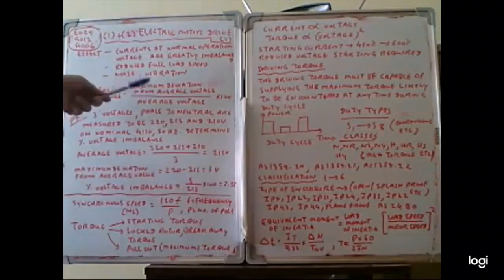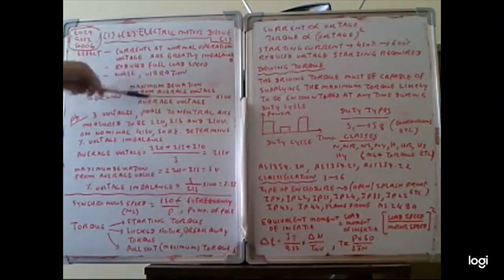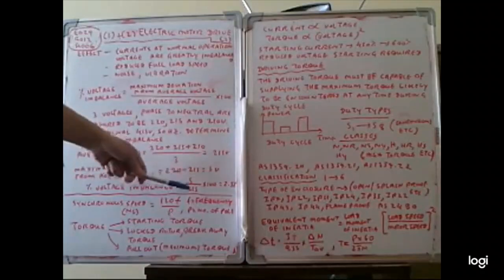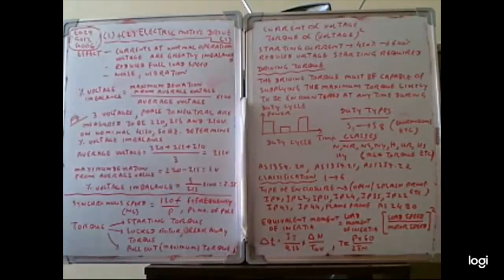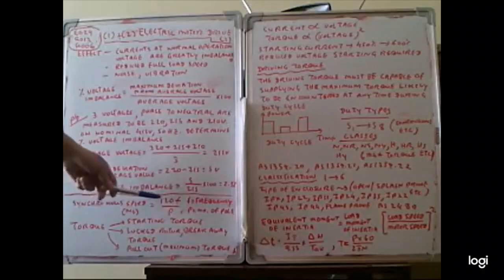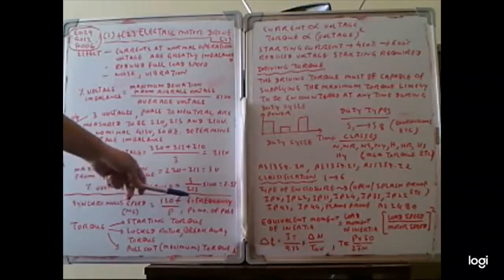Then we substitute into the formula: maximum deviation from the average voltage divided by average voltage, multiplied by 100. So 5 divided by 215 multiplied by 100 is 2.33%. When the motor is running, we can calculate the synchronous speed. Synchronous speed is equal to 120 F divided by P, where F is the frequency and P is the number of poles.